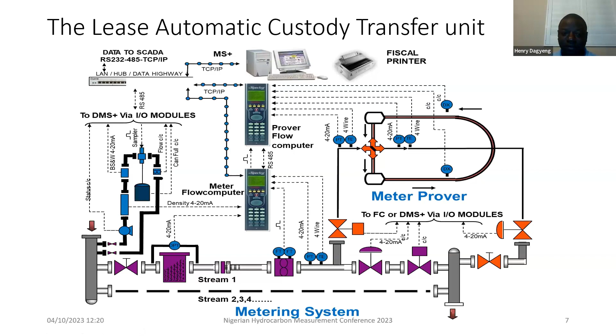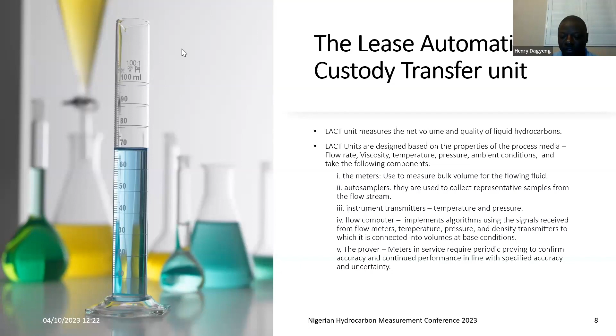So essentially what the LACT unit does is measure the net volume and quality of liquid hydrocarbons, just like I've mentioned. Usually a LACT unit is basically designed based on the process media: the flow rate, the viscosity, the temperature, the pressure, and also ambient conditions. As I mentioned, you have the meters, the auto sampler, the instrument transmitters, the flow computer, and of course the prover.